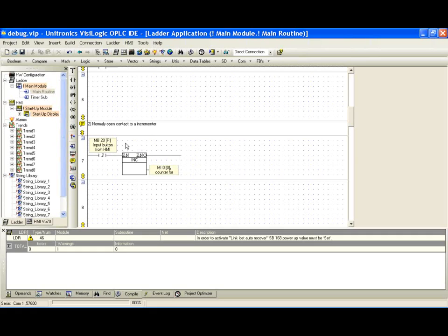If we have a function, say a communication function, where we want to issue just one command, and we place this incrementer block on it and it starts counting up at a very fast rate, we'll see that we're not activating it just once. We'll see that we're activating it many times.